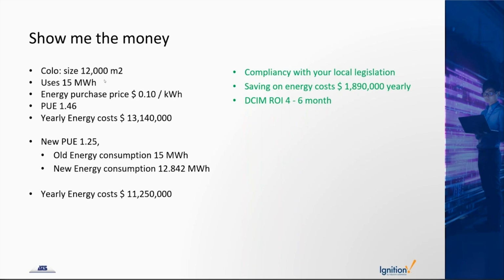So this is a little bit bigger data center. It's a co-location site of 12,000 square meters. They're using 15 megawatt hours. So it's 3 times as big as the example. And the energy purchase price is $0.10 per kilowatt-hour. If you have a PUE of 1.46, your yearly energy cost will be $13.1 million US. If you take the step we just showed you, and the PUE is lowered from 1.46 to 1.25, your energy consumption is lowered from 15 to 12.8 megawatts. So your new energy cost will be $11.2 million US. That means you will be saving $1.8 million yearly by just taking some simple steps.